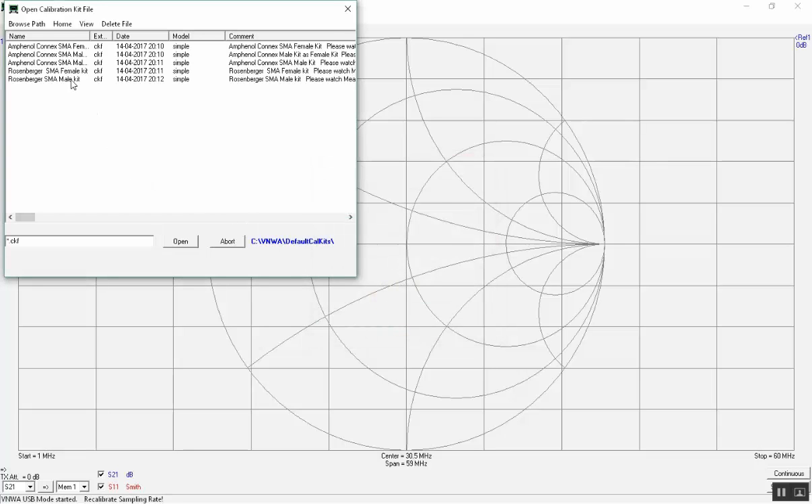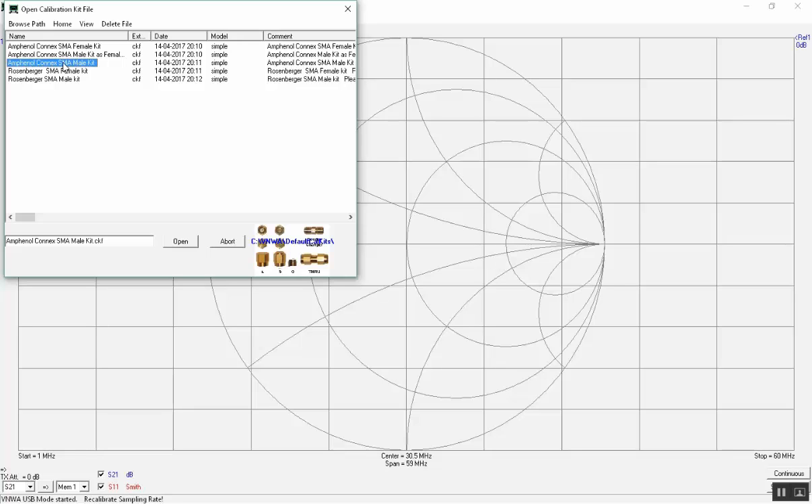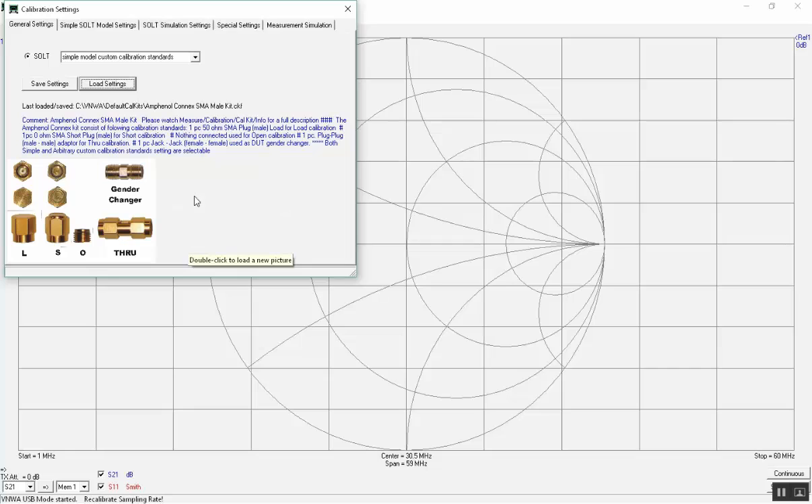We expand the column for the naming of the calibration kit to see its full description and choose the Amphenol Connex SMA male kit. When the kit is marked we see a small picture in the lower right corner of the components in the kit. When loaded by a click on Open, there is a full description of the calibration kit and larger pictures of its components: load, short, open, and the two male-female through adapters.